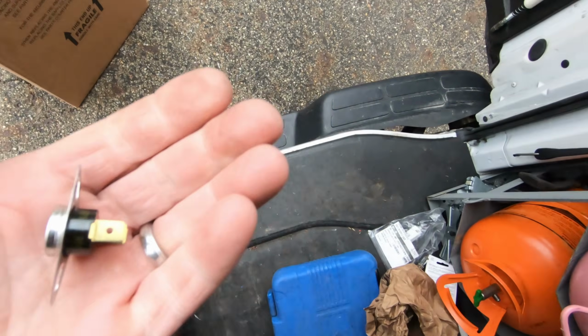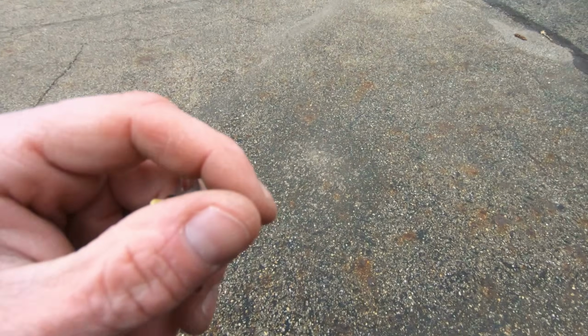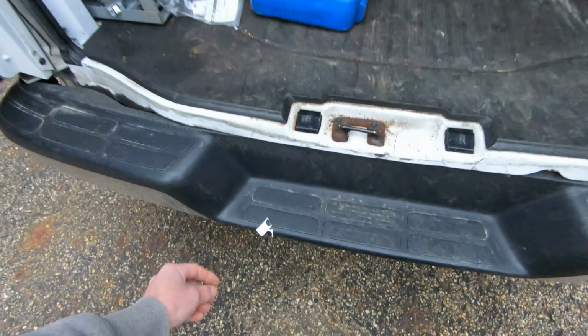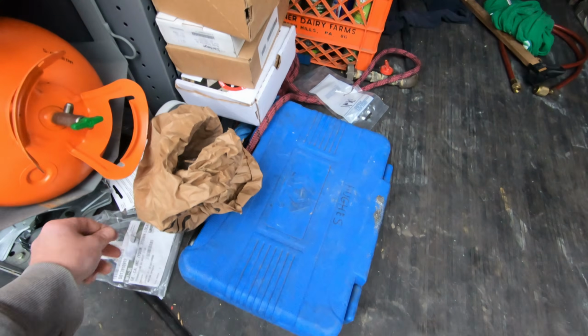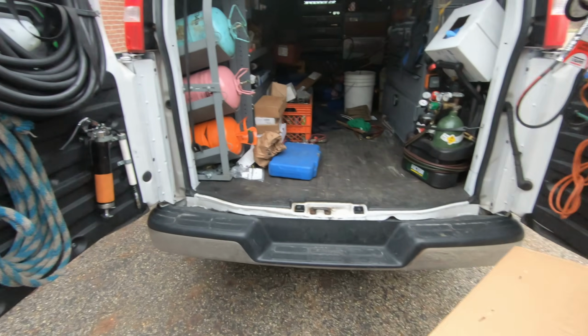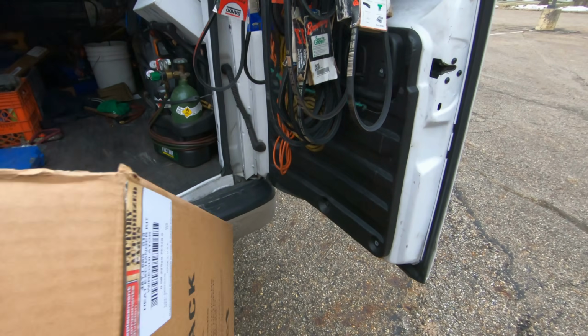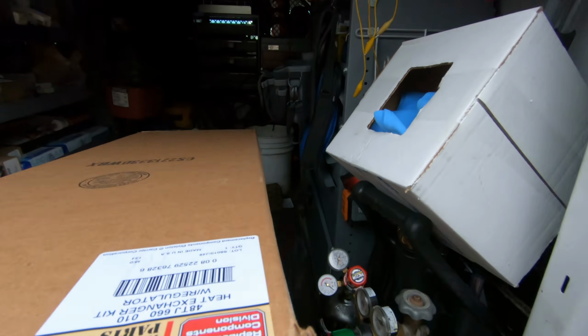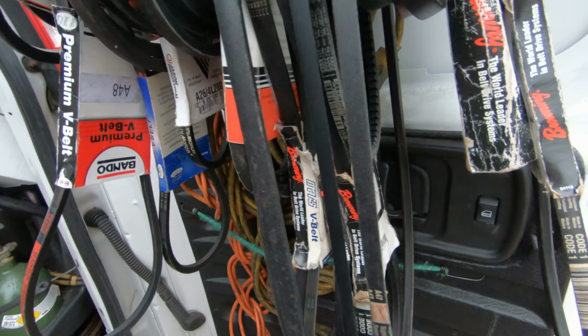All right guys, I got one from a different manufacturer, but it's only a few degrees higher than the one that was in there. The one that was in there calls for 135, this is a 155. We're going to replace it with the OEM limit when we come back, because that blower motor is going to need replaced. And we're going to write up the blower motor, limit, and new belt.